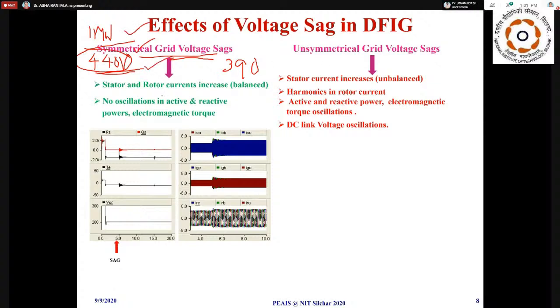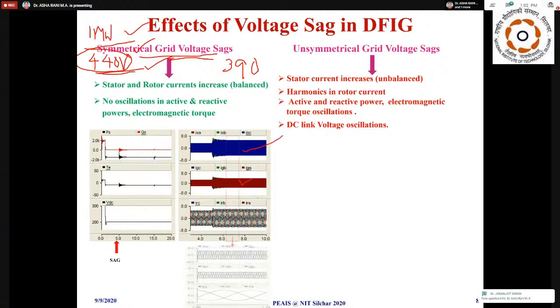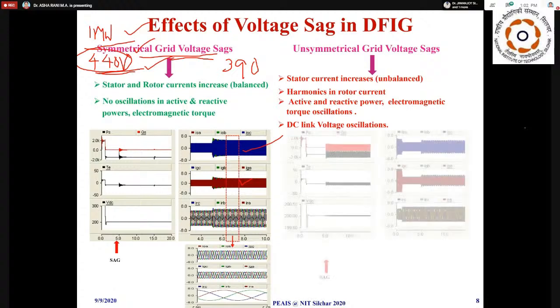Nothing else will happen. If all the phases have a balanced grid sag, nothing will happen. The only thing is that you will be able to pump the same power, if you are within the rating of the machine, with a higher current that you can see here. Only the current will increase. So it is still stable, unless you exceed the rated current capacity. But that will not be the scenario in the case of unsymmetrical sag.